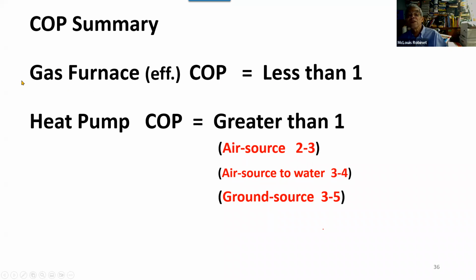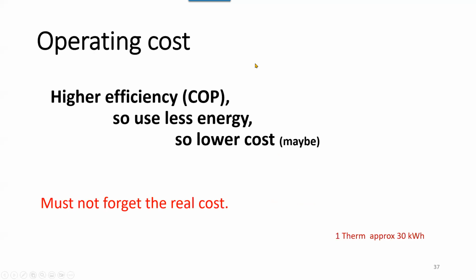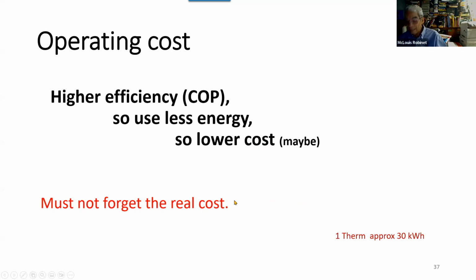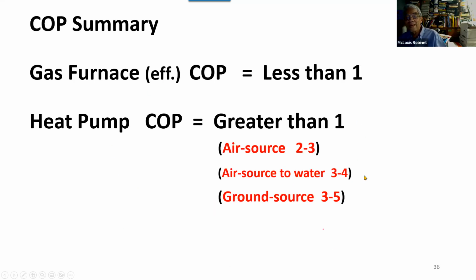So if we round the gas furnace off to 1, an air source heat pump is 2 to 3 times more efficient than a gas furnace. For an air source to water heat pump, where you're using air as the source but using it to heat water, the coefficient of performance is 3 to 4. The ground source heat pump has a coefficient of performance of 3 to 5. These numbers will increase as the technology improves. This number will never change. Okay, so that's what it's all about. And so again, this is the enabling technology for electrification.